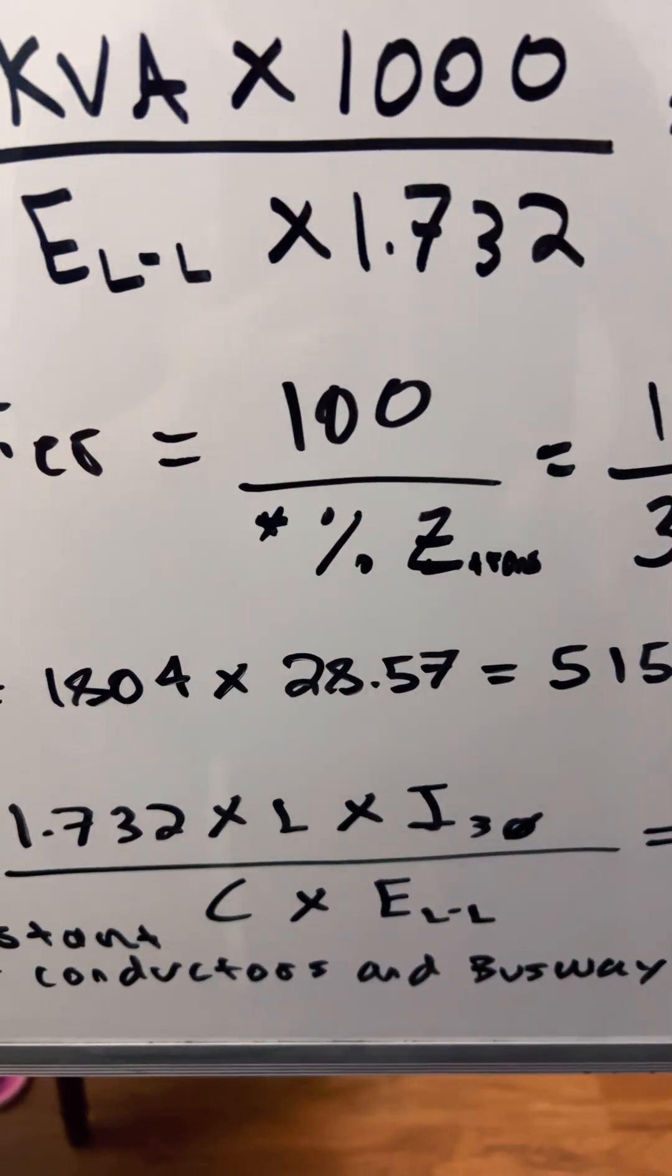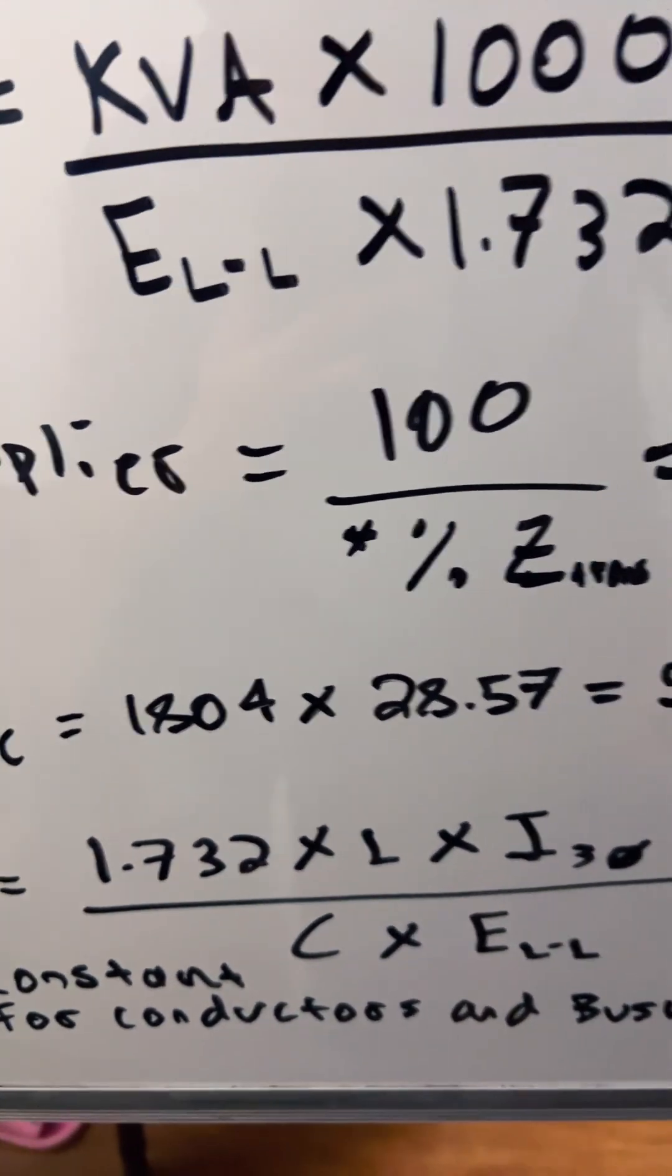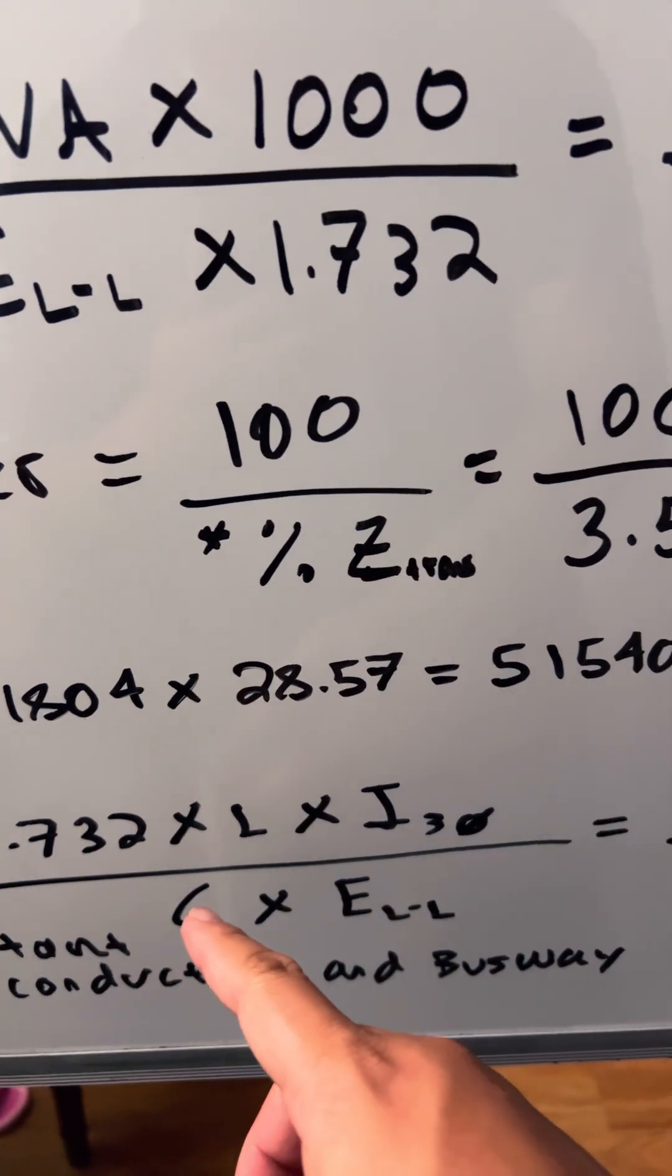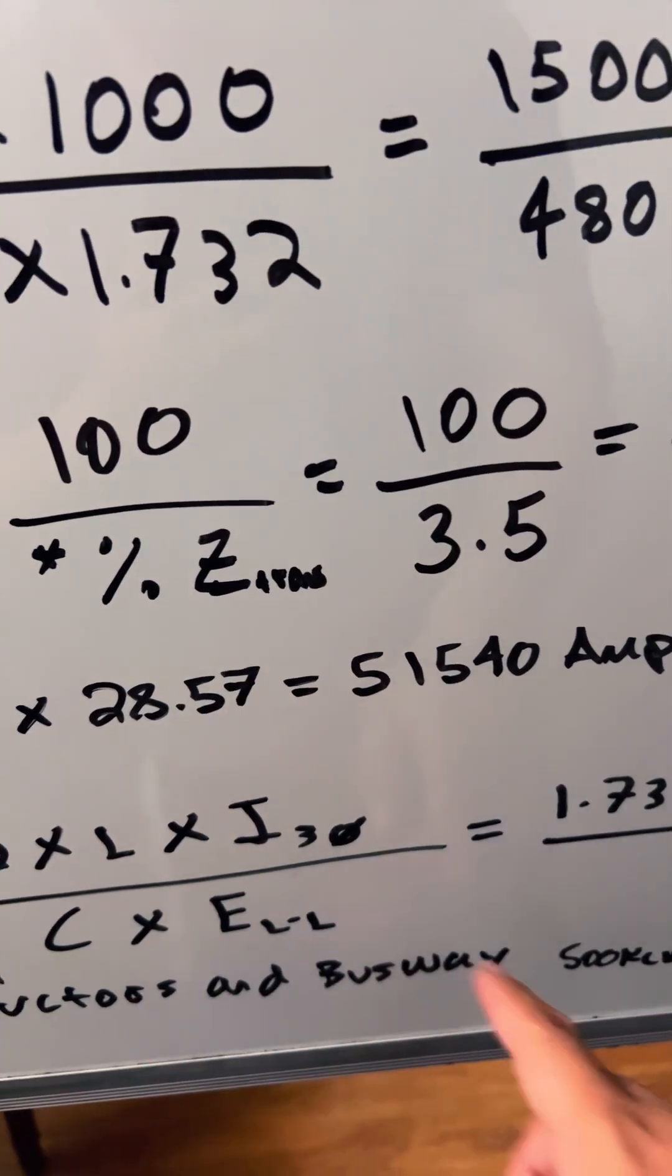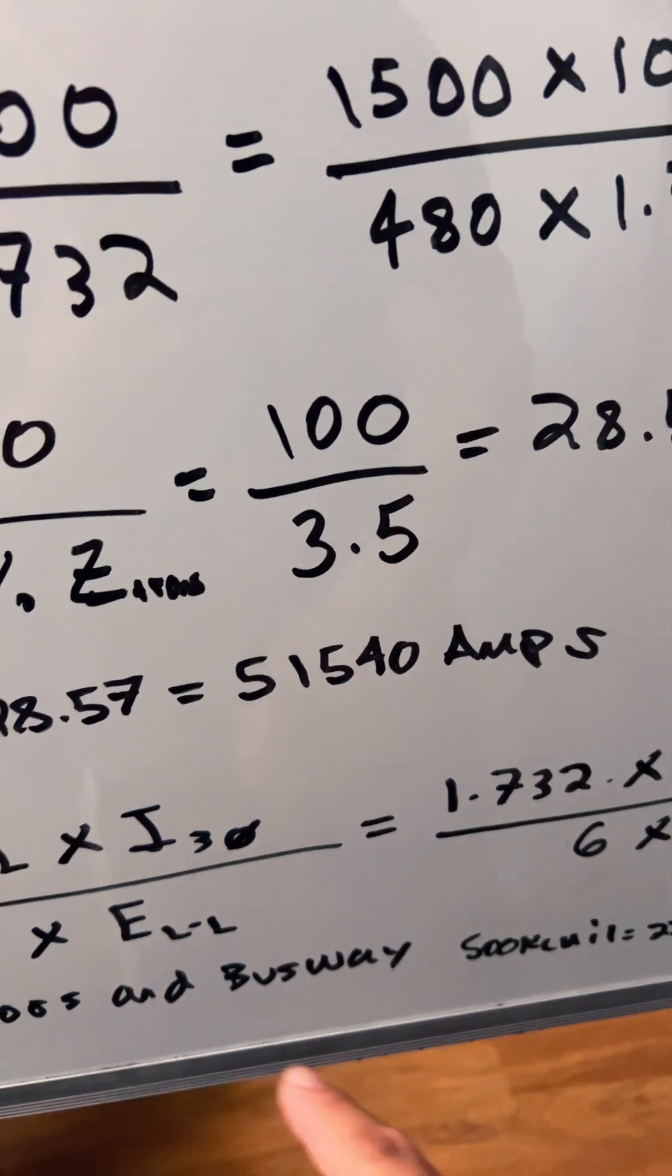Then we find the factor, which equals 1.732 times L (the length) times the three-phase current, divided by C (the constant for conductors and busway) times the line-to-line voltage. Plugging in the numbers gives us 0.0349.